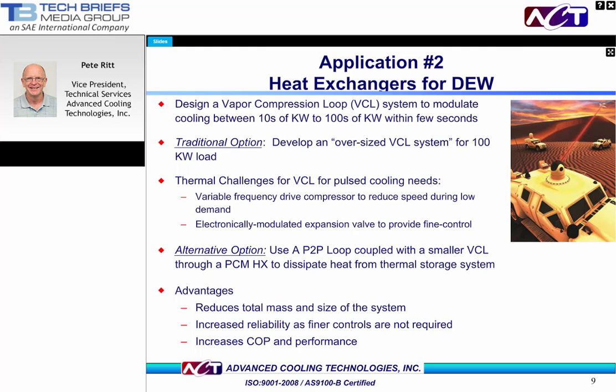In addition to being large and bulky, these systems require additional controls, such as variable frequency drive motors to reduce the speed during off periods, and expansion valves, which have finer control. An alternative solution is to introduce a P2P loop that is coupled with a smaller vapor compression loop and a PCM heat exchanger, PCM phase change material, to store and dissipate the waste heat. This solution reduces the total overall mass, eliminates the need for some more precise controls, and improves coefficient of performance, COP, for the entire system.